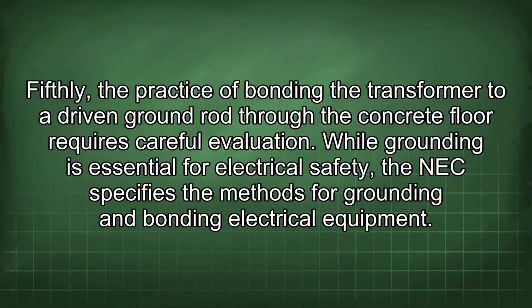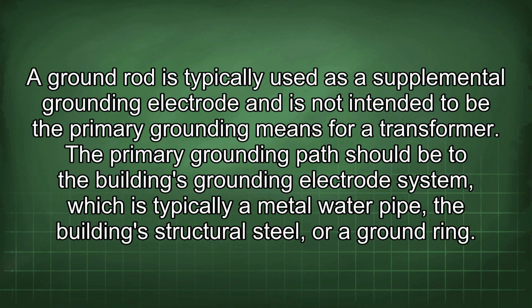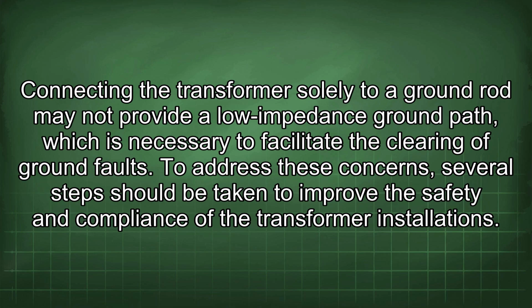Fifthly, the practice of bonding the transformer to a driven ground rod through the concrete floor requires careful evaluation. While grounding is essential for electrical safety, the NEC specifies the methods for grounding and bonding electrical equipment. A ground rod is typically used as a supplemental grounding electrode and is not intended to be the primary grounding means for a transformer. The primary grounding path should be to the building's grounding electrode system, which is typically a metal water pipe, the building's structural steel, or a ground ring. Connecting the transformer solely to a ground rod may not provide a low-impedance ground path, which is necessary to facilitate the clearing of ground faults.